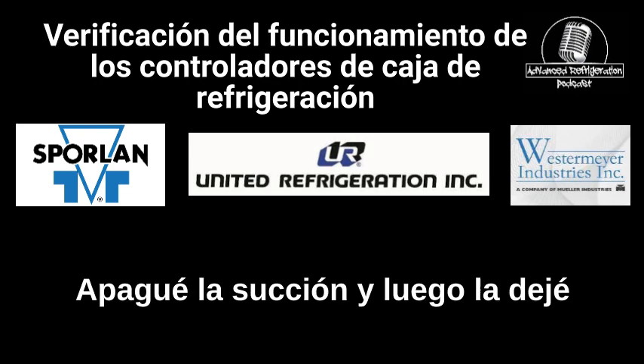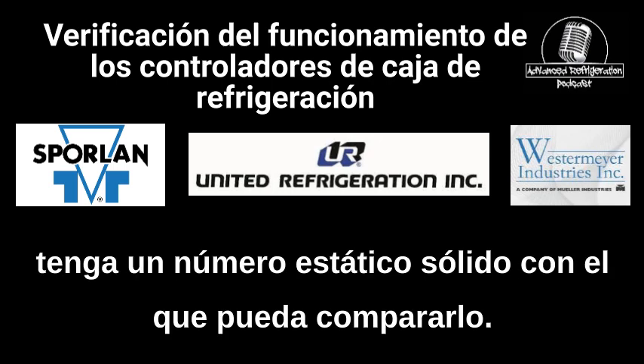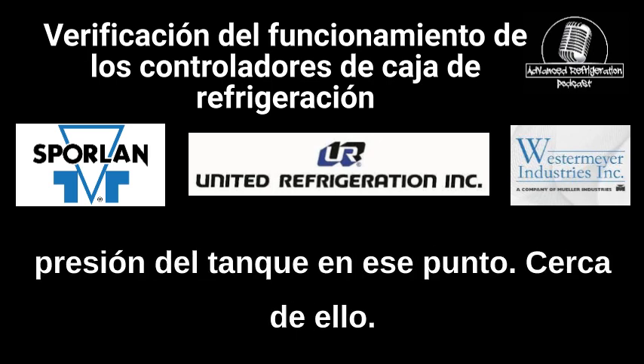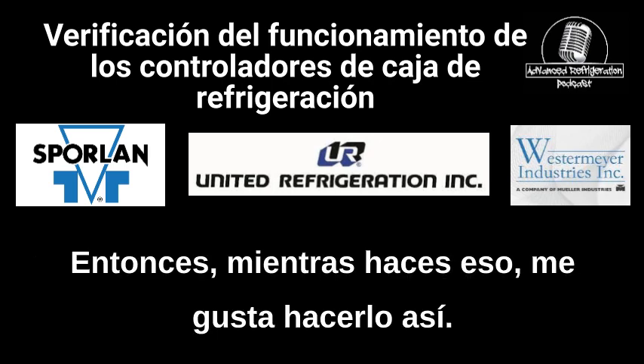I shut off the suction and then I let it build up where it equalizes. And then that way I have a solid static number I could check it against. Yeah. So essentially you're checking it out. It'll basically end up being off the flash tank pressure at that point. Close to it. Yeah, close to it.